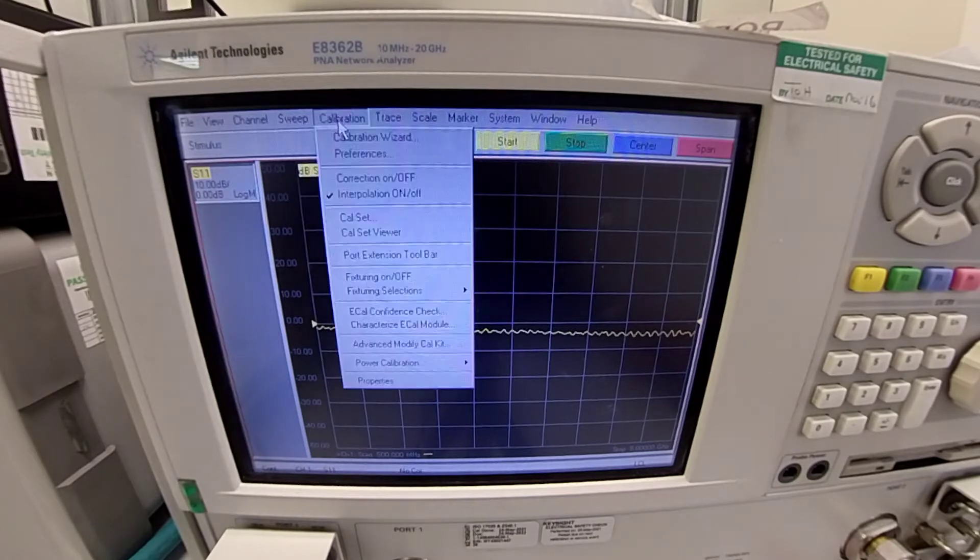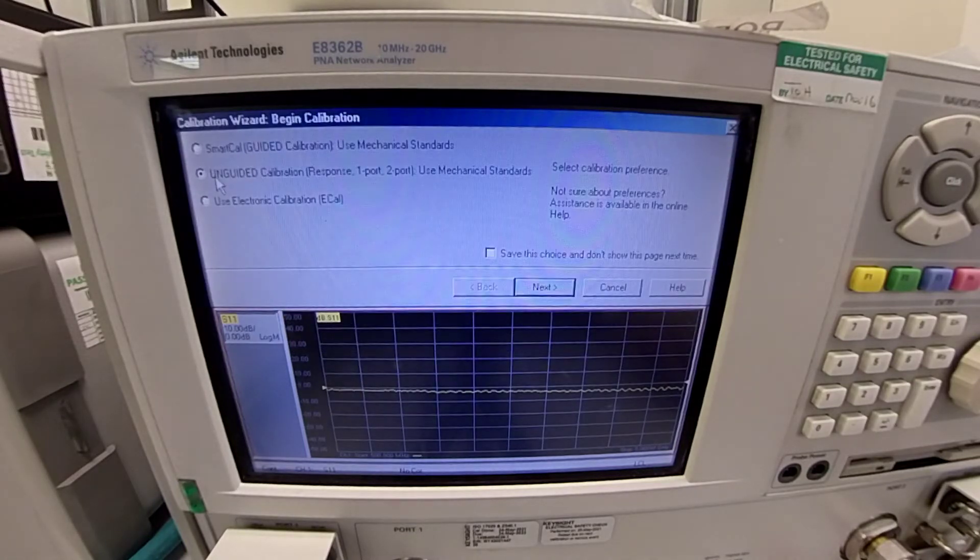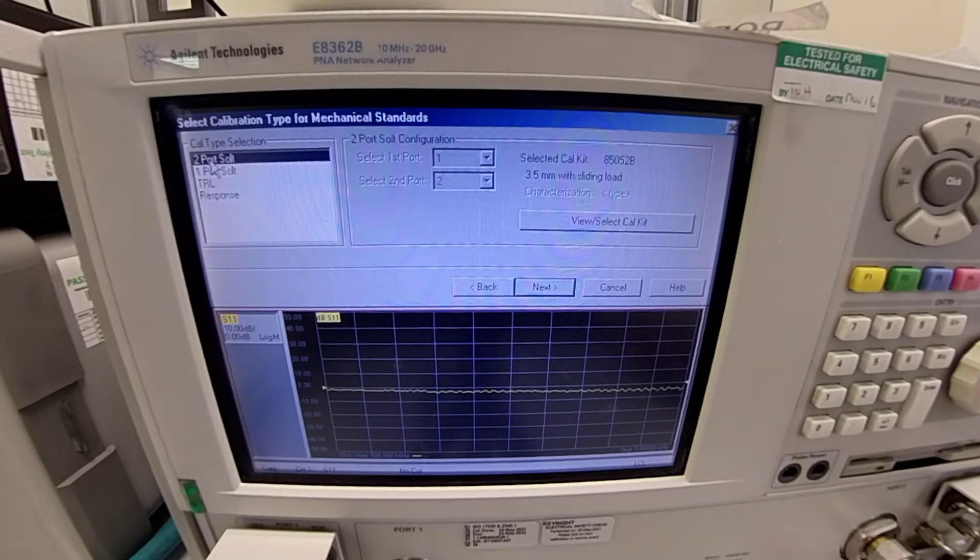We go towards the calibration, calibration wizard, unguided calibration, use mechanical standards. In the calibration type, we select 2-port calibration.